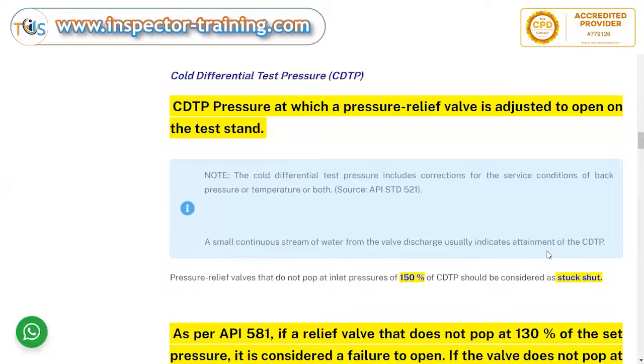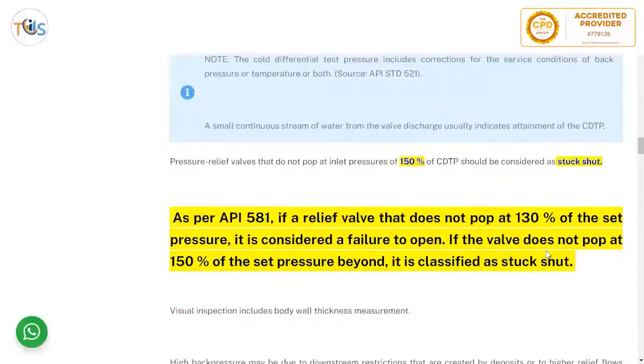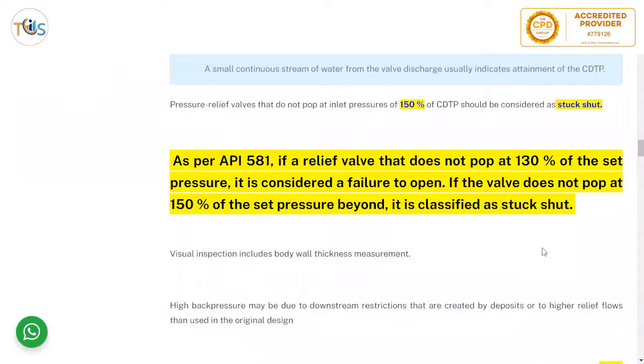The cold differential test pressure includes corrections for service conditions such as back pressure, temperature, or both. A small continuous stream of water from the valve discharge usually indicates that the CDTP has been reached. Pressure relief valves that do not pop at 150% of CDTP should be considered a stuck-shut valve. As per API 581, a relief valve that does not pop at 130% of the set pressure is considered a failure to open; if it does not pop at 150%, it is classified as stuck-shut.